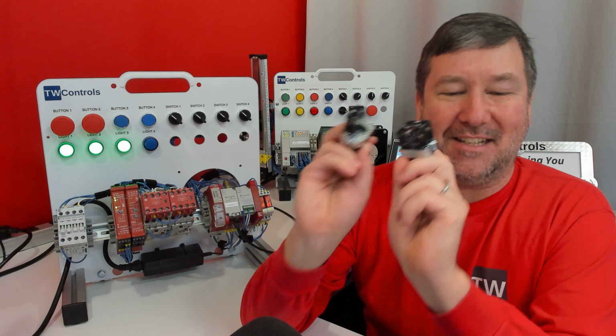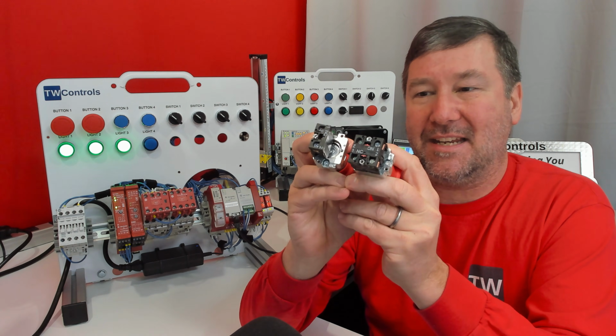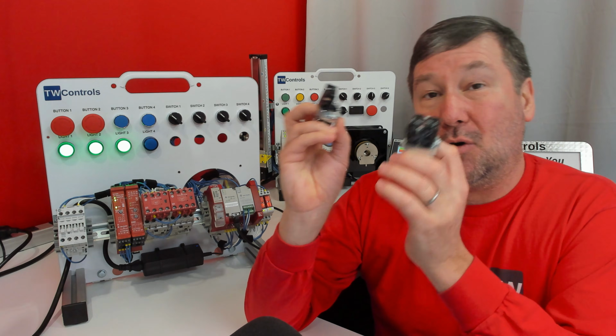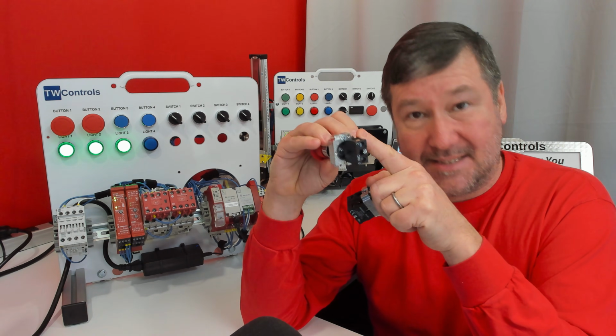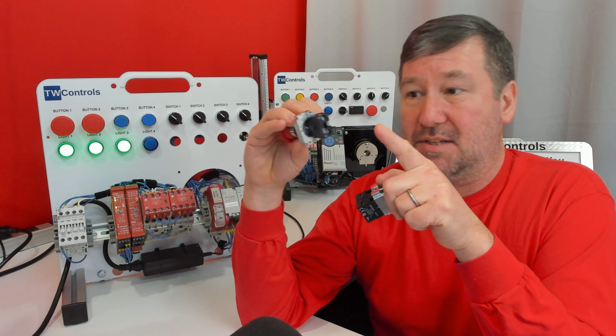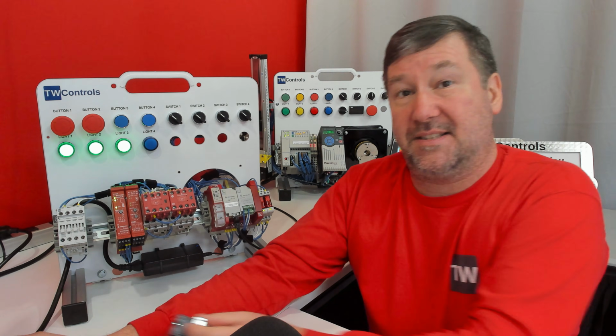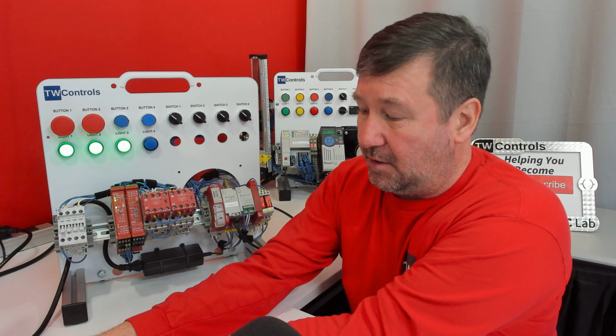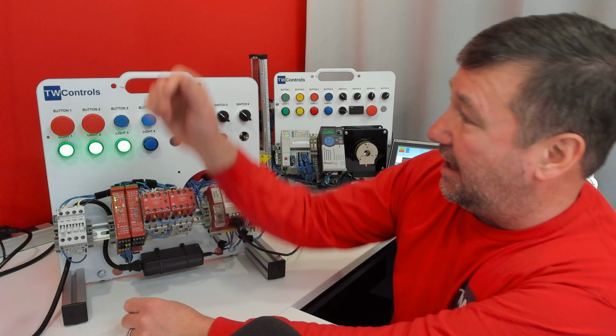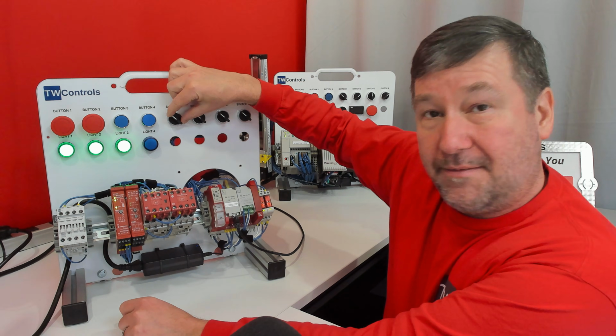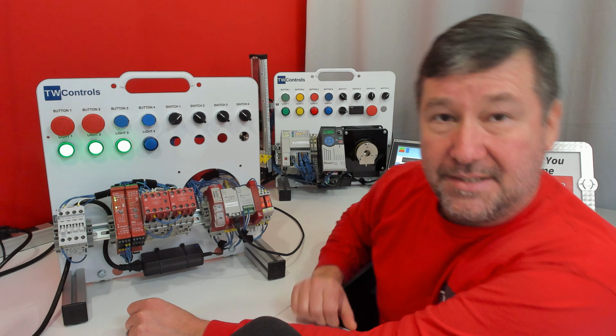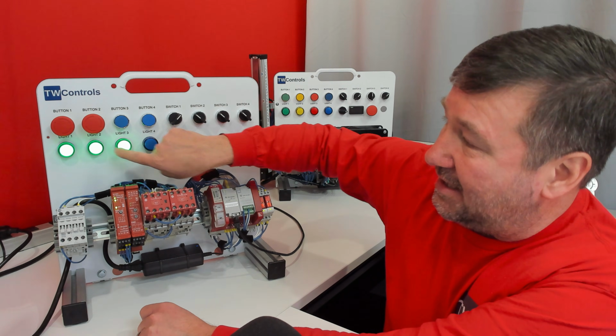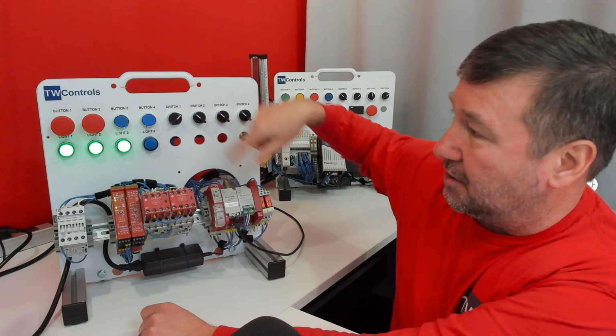Now let's get back to talking about our single contact e-stop failure. So if a contact gets stuck closed, or this contact comes off, or heaven forbid somebody jumpers it, which hopefully nobody in modern machines is doing now, then we'll have a single point failure. And I have switch 1 to simulate that. So pay attention to the 3 safety circuits.